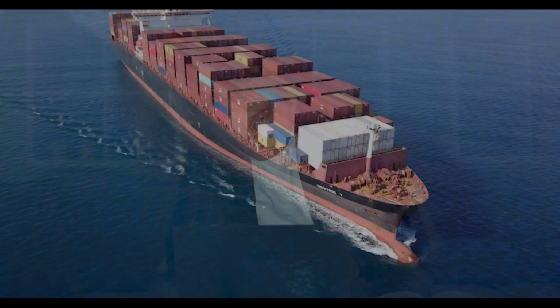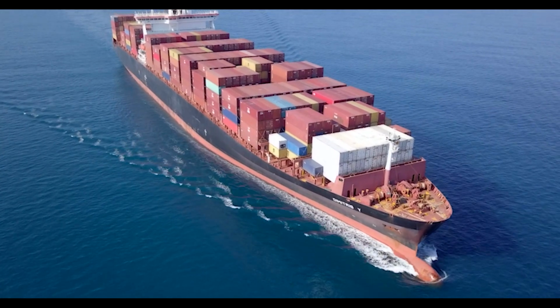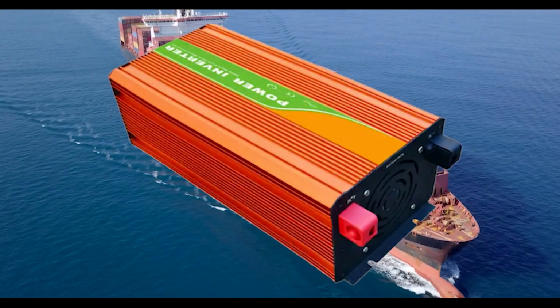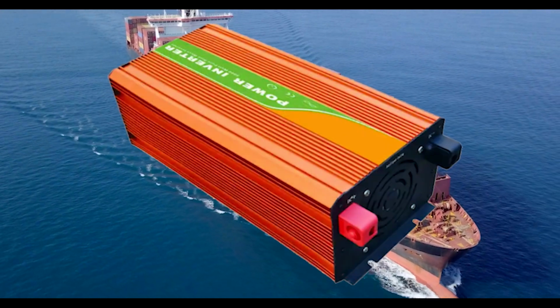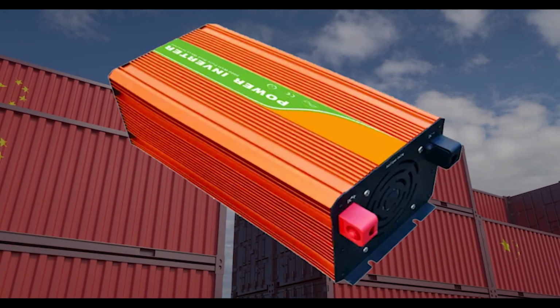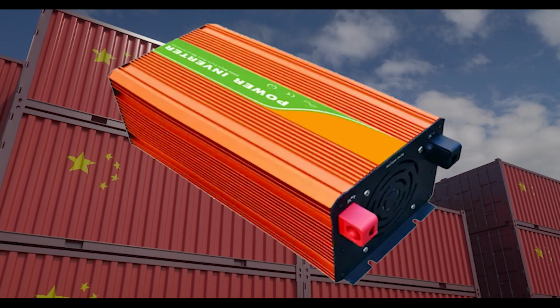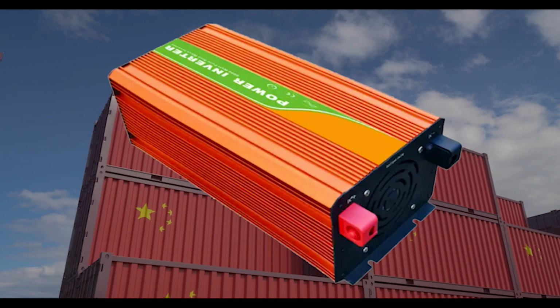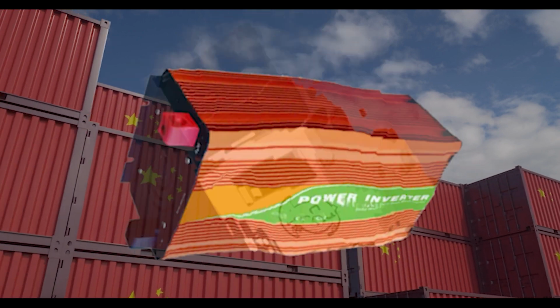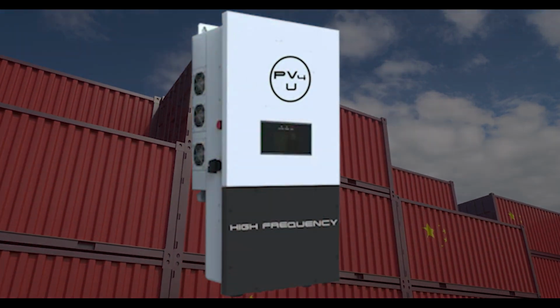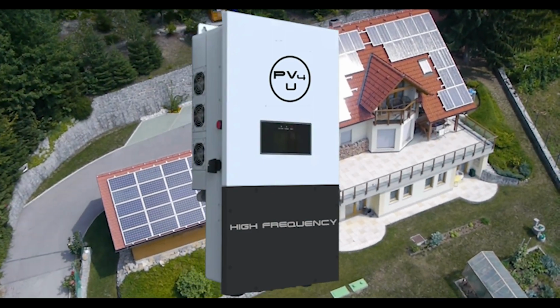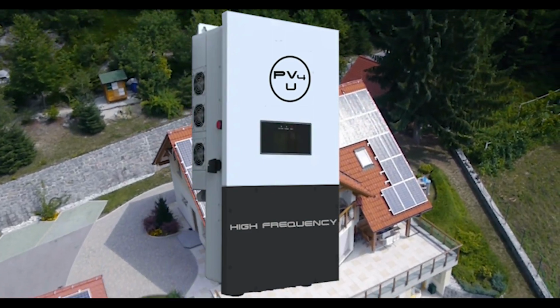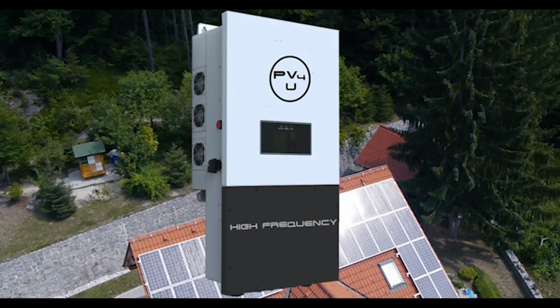And despite all of the early high-frequency inverter failures that resulted in damaged appliances and even fires, the Chinese are still flooding the US market with these poorly designed, unsafe, high-frequency inverters. Only this time, these manufacturers are stuffing these lightweight, short-lived, low-surge inverters into larger, more modern-looking metal boxes with little to no improvements to this outdated high-frequency technology, with claims that they can safely power your entire home.